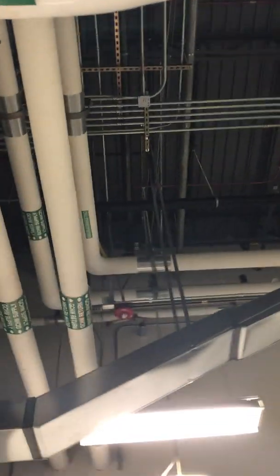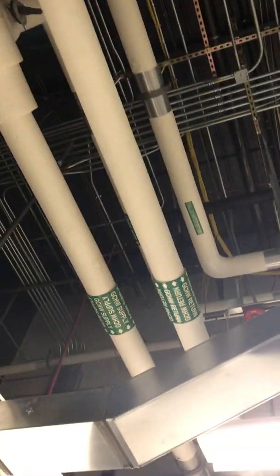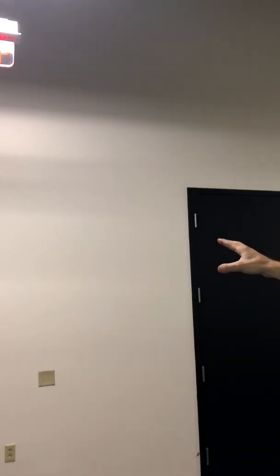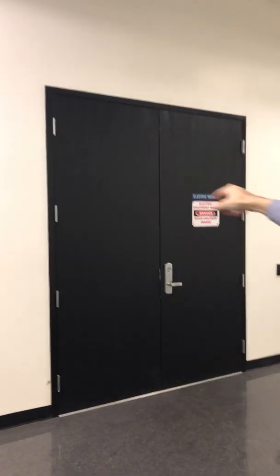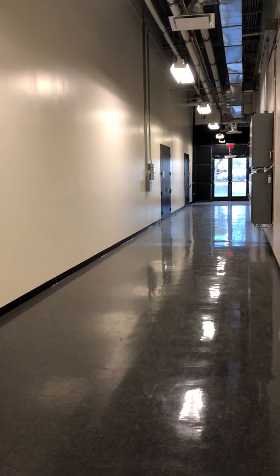In here, you can see where the chilled water supply and return splits. Because of the high heat load, when electric room A and electric room B are operating, rooftop package cooling wasn't adequate, so we designed it to operate with CRAC units.